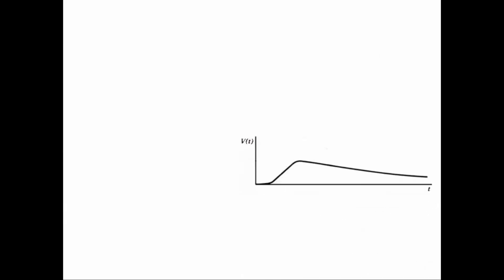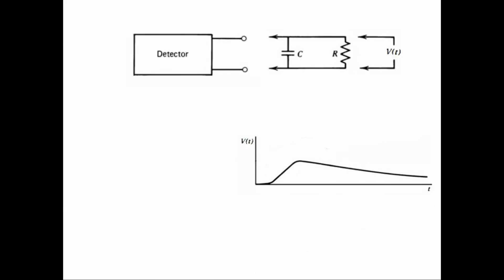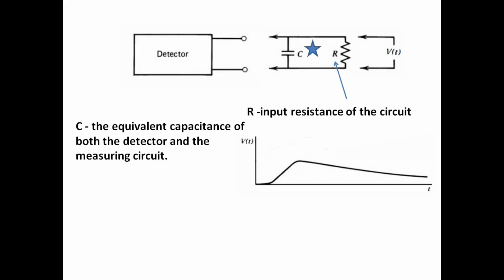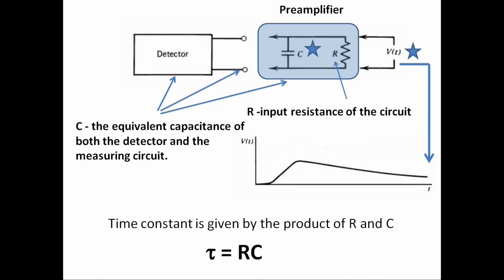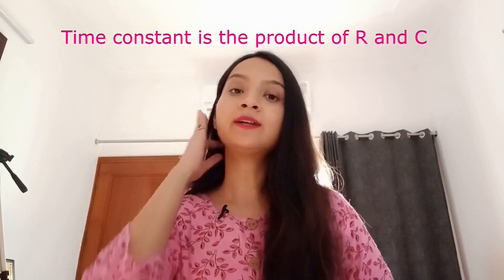The nature of the signal pulse produced from a single event depends upon the input characteristics of the circuit to which the detector is connected. As you can see in this equivalent circuit, R represents the input resistance of the circuit and C represents the equivalent capacitance of both the detector itself and the measuring circuit. For example, if a preamplifier is attached, R is its input resistance and C is the summed capacitance of the detector, the connecting cable, and the input capacitance of the preamplifier. Vt is the time-dependent voltage across the load resistance, and it is this fundamental signal voltage on which pulse mode operation is based.